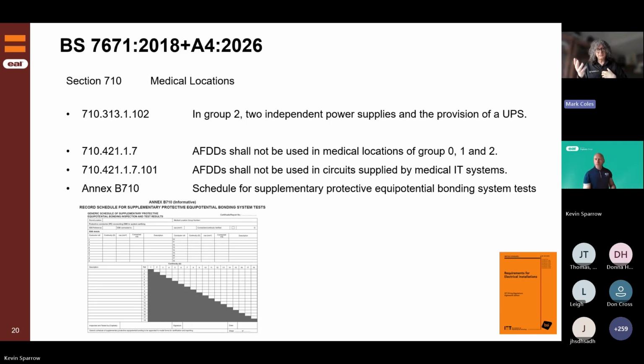So you've got protective equipotential bonding, supplementary protective equipotential bonding systems installed in this area to make sure you keep potentials down. Now then, there's a requirement in 710 to provide a schematic diagram to show where that one goes to that one, that one goes to that one. It's all numbered. Then you have what's on the screen here, a supplementary protective equipotential bonding recording schedule.